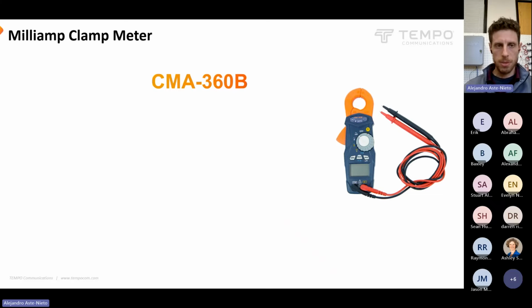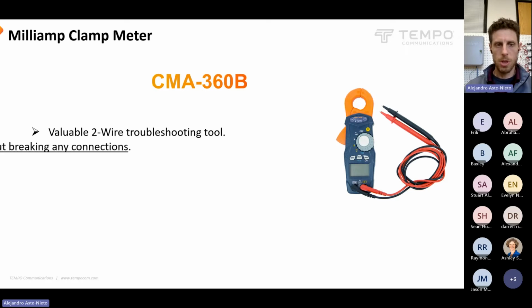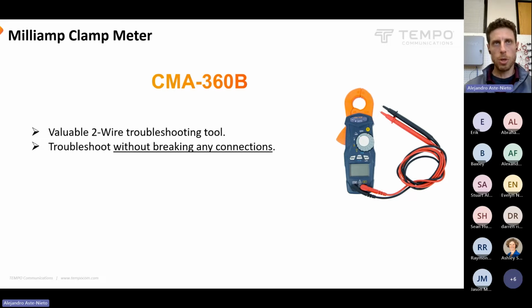So now, talking about the clamp meter, the CMA 360B. The reason why a clamp meter is such a valuable tool is because you can troubleshoot these systems without breaking connections. You can troubleshoot 2-wire systems without a clamp meter, but that involves taking the wire path apart and breaking it in half and seeing if your problems go away, and then reattaching and then breaking another section, and sometimes taking measurements of resistance or voltage along the way. But obviously, when you're breaking connections, not only do you have to get a little bit more dirty, but you have to replace these connections, and those are not free. You have to spend the money on more splices. And then you might be breaking good connections and introducing new problems on the second time around when you have to resplice.